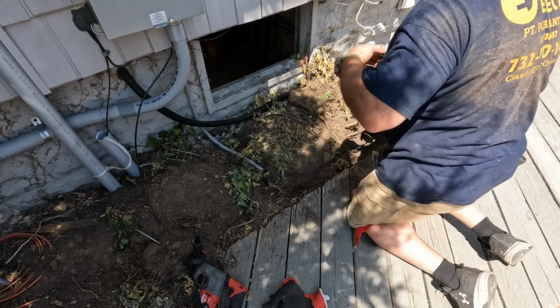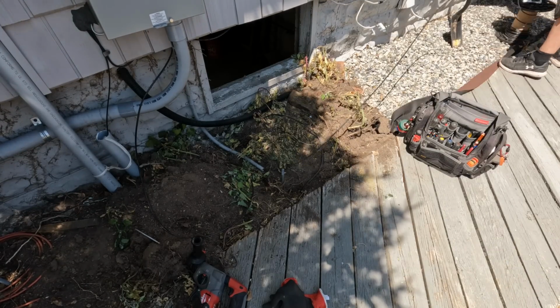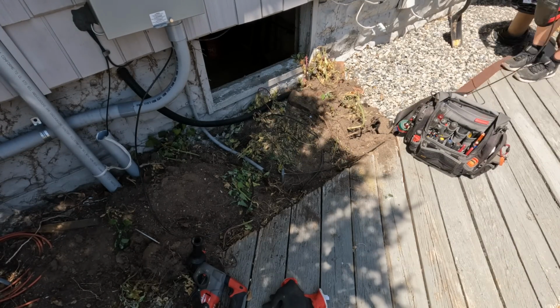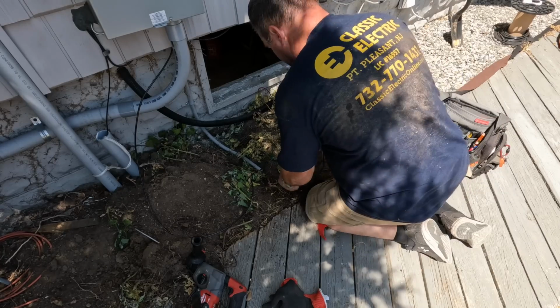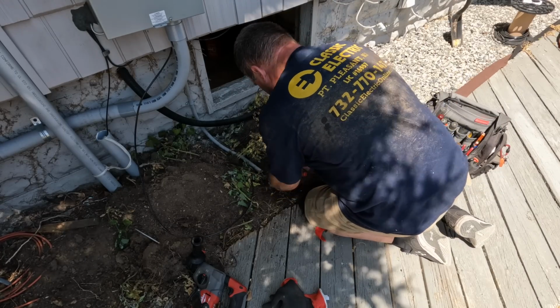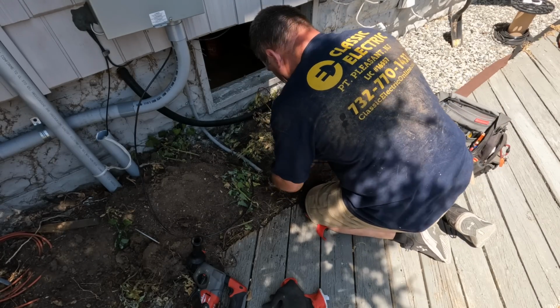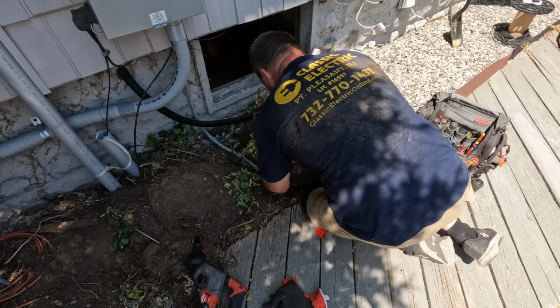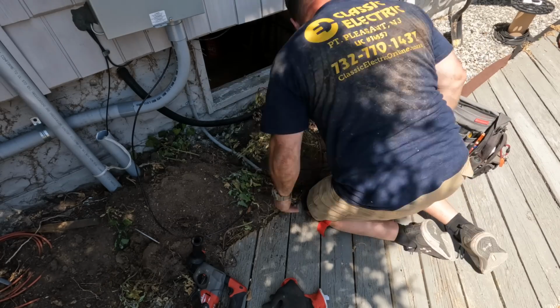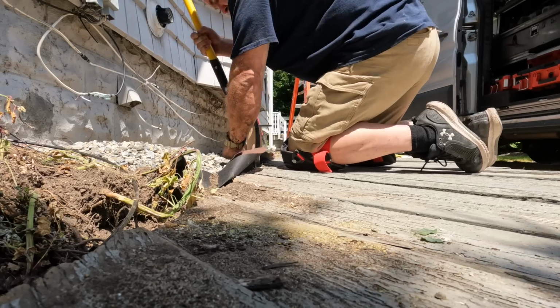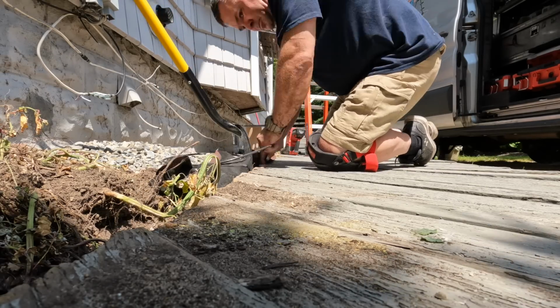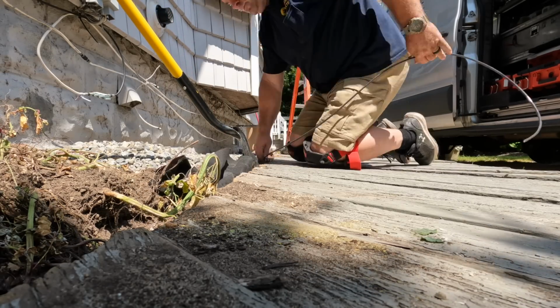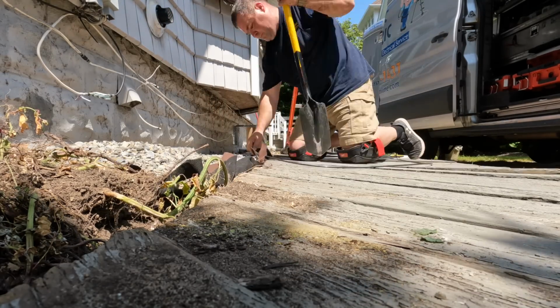The utility company here requires that if you're going to run that grounding electrode conductor on the outside of the house like I have here, that you protect that particular conductor from physical damage. So that's why I ran this 1/2 inch PVC. I sleeved my number 6 copper through the PVC and attached it later, you'll see, to the grounding bridge.